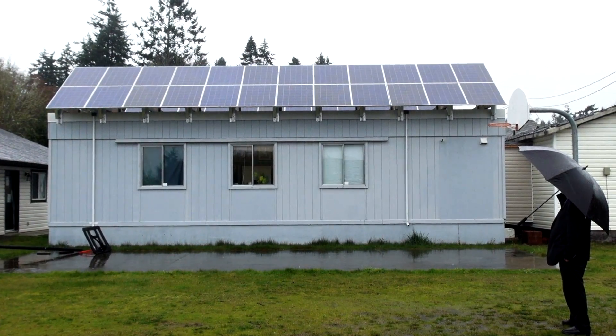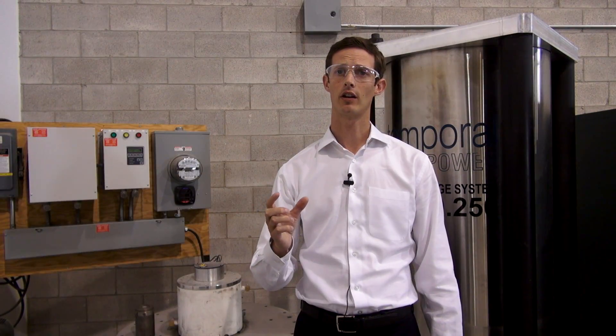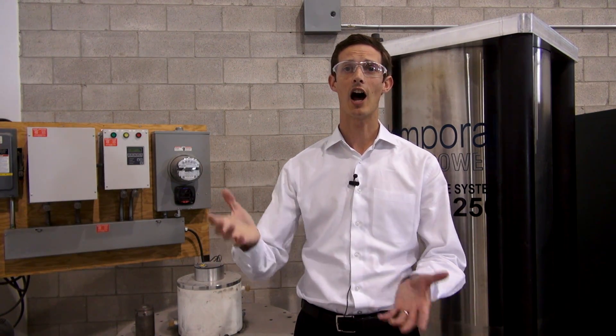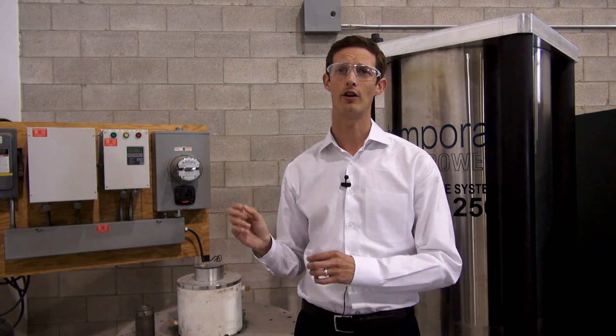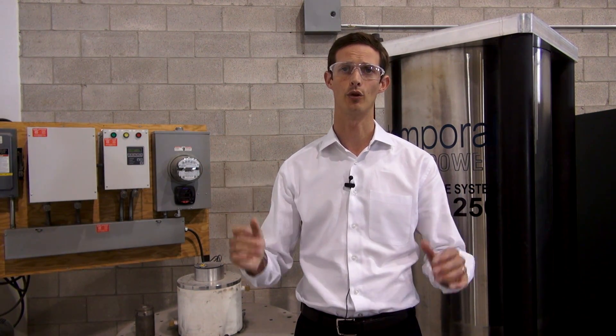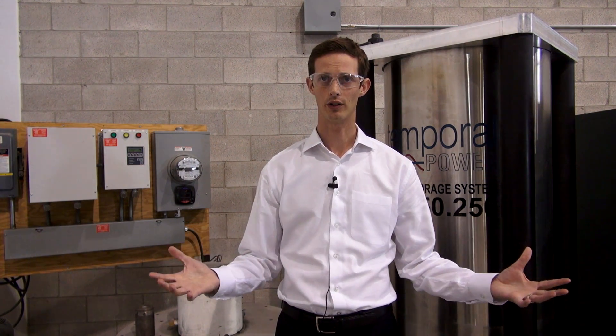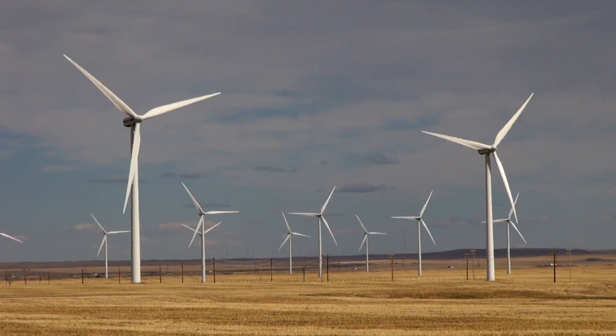Once the electricity grid is getting about 20% of its electricity from renewable energy, you need energy balancing. On isolated grids where you get high levels of renewables very quickly, this type of energy storage is required to operate the grids stably and allow them to get up to 30%, 40%, 50%, even 60% renewables — and potentially even higher. Temporal Power is installing two larger-scale systems in Ontario right now: one is a 5-megawatt system in southwest Ontario providing power quality on a distribution line with significant wind, and the other is providing energy balancing to the Ontario power system through the system operator.